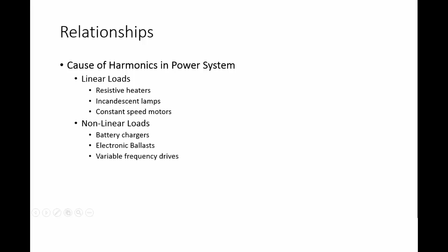Resistive heaters, incandescent lamps, and constant speed induction and synchronous motors are examples of linear loads. On the other hand, most loads are nonlinear, and the waveforms of their current and voltage are not purely sinusoidal. Waveforms in nonlinear loads are about 60 Hz and contain numerous additional waveforms of other frequencies superimposed upon it. The multiple frequencies are harmonics of the fundamental. Examples of nonlinear loads are battery chargers and variable frequency drives.